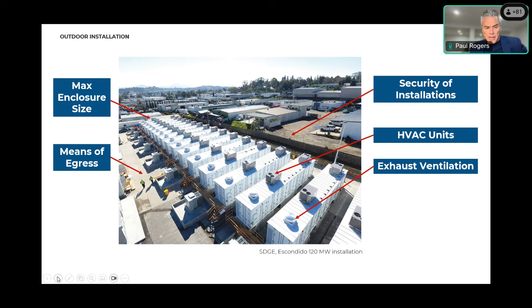Okay, again, this is showing you distances here. For an outdoor installation, they're giving the example of a 2 megawatt, 4 megawatt hour system, so it's a 2 hour system per enclosure. If you can take a look at number two there, they're 6 inches apart, right? It's showing the separation distance between cabinets is 6 inches apart. How did they do that? They actually tested it that way.